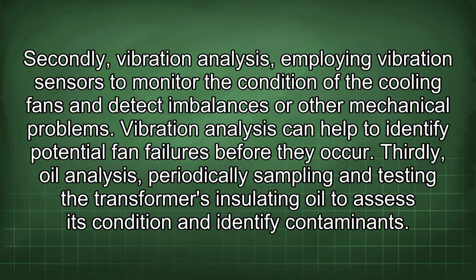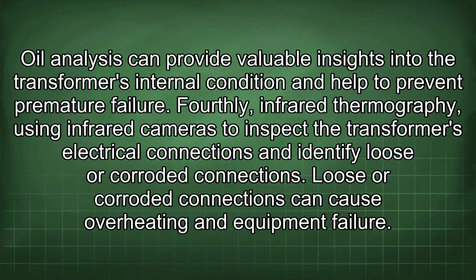Thirdly, oil analysis, periodically sampling and testing the transformer's insulating oil to assess its condition and identify contaminants. Oil analysis can provide valuable insights into the transformer's internal condition and help to prevent premature failure. Fourthly, infrared thermography, using infrared cameras to inspect the transformer's electrical connections and identify loose or corroded connections. Loose or corroded connections can cause overheating and equipment failure.